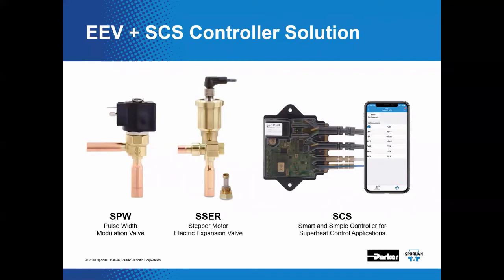All right, so Sporlan offers a simplified electronic solution for these type of scenarios. The superheat control system, as shown here, also known as the SCS, is a controller that's recently released by Sporlan. This controller is encapsulated, so it can be placed in the refrigerated environment, right, without fear of moisture or any debris affecting this controller. Additionally, it was designed to be easy to install. It incorporates the temperature sensor, the pressure transducer cable, the valve cable, and also the power cable into the controller. And I'll cover more of that in a couple slides.